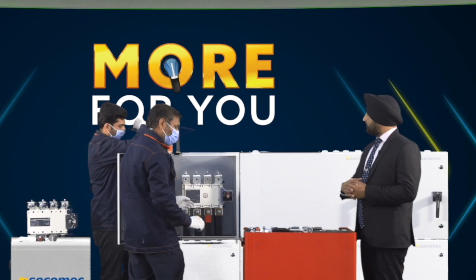Because our new product has a higher width and spread contacts, those spread contacts will help me terminate the bus bars already on the installation. As you can see in this panel, although this is copper bus barring, on your side you could also have aluminium bus bar termination possible, because of this spread contact which is part of our new SIRCOVER range.